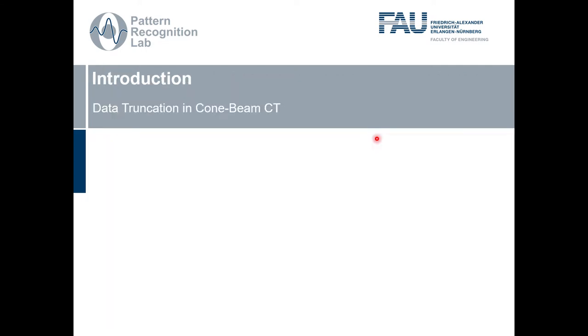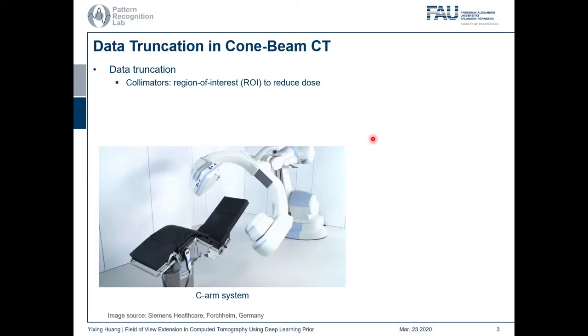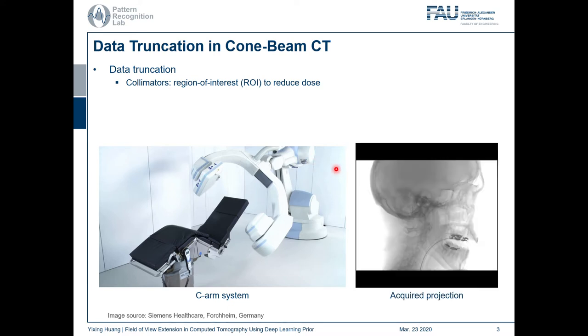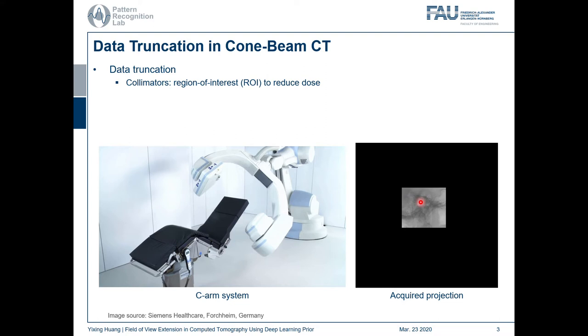Let me introduce data truncation in cone beam CT. The problem of data truncation arises in two scenarios. The first scenario is that in certain clinical applications, only a certain region is of interest. For example, if we want to deploy a stent to a certain artery or get tissue samples with biopsy, some X-ray collimators will be placed between the X-ray source and the detector to reduce dose. If we are only interested in the area near the ear, inside a red box, then with the collimator, only this region is acquired and the projections are truncated in the horizontal direction.